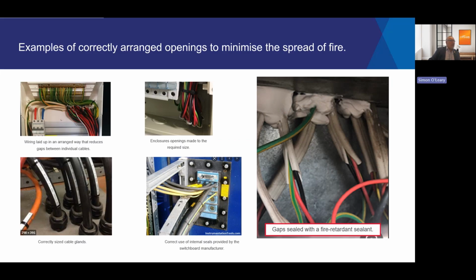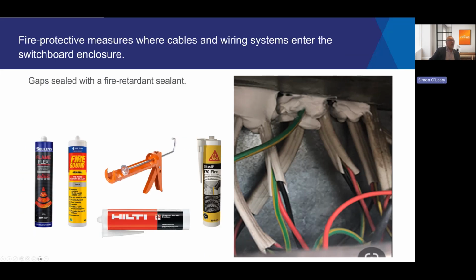Ways that you can ensure that your cables enter into switchboards through close-fitting holes include using a number of methods: laying up the cables in a way that reduces any gaps between the conductors and cables; making sure the enclosure entry holes are made to the right size, so the cables will fill up the holes; correctly sized cable glands, and also using correct internal seals provided by switchboard manufacturers. And one of the easiest ways to address the close-fitting holes is using fire-rated sealants, and there's a number of those on the market that are available.